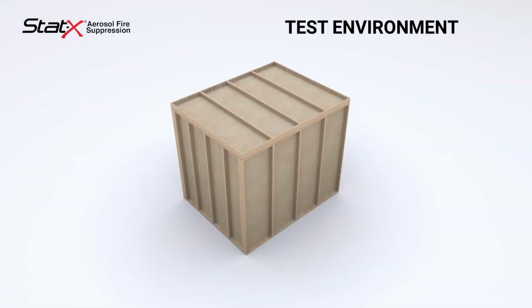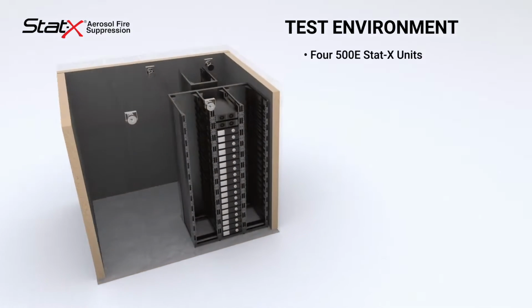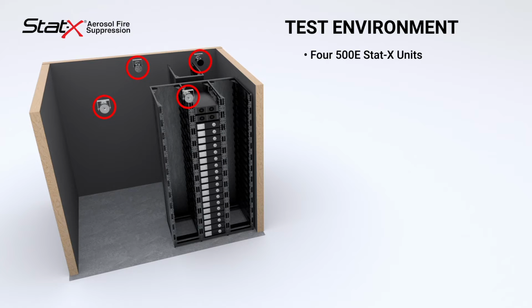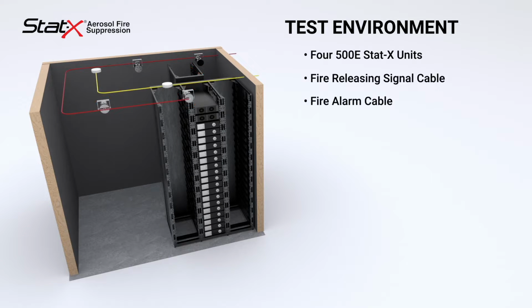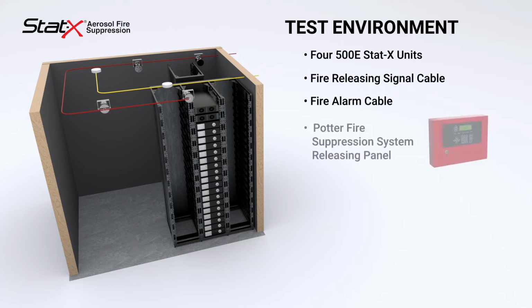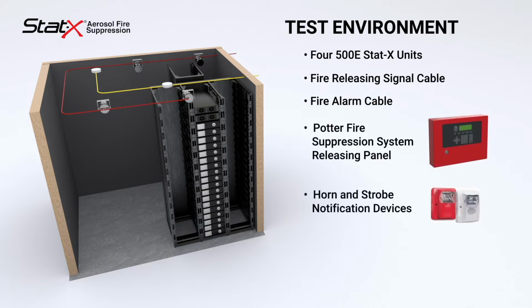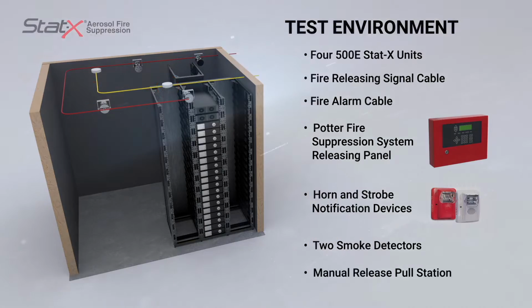The test environment consisted of a 2.3 meters wide by 2.5 meters long enclosure with 4 500E StatX units, fire-releasing signal cable, fire alarm cable. Also included were a Potter fire suppression system releasing panel, horn and strobe notification devices, 2 photoelectric first and second smoke detectors providing cross-zone detection, and a manual release pull station.